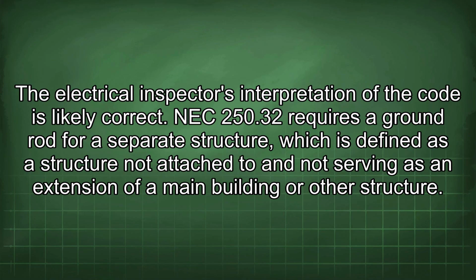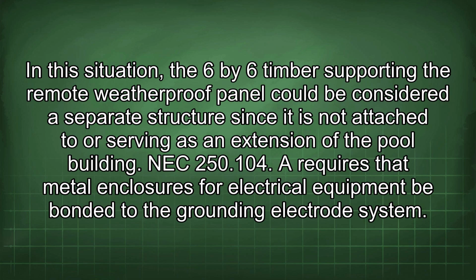The electrical inspector's interpretation of the code is likely correct. NEC 250.32 requires a ground rod for a separate structure, which is defined as a structure not attached to and not serving as an extension of a main building or other structure. In this situation, the 6x6 timber supporting the remote weatherproof panel could be considered a separate structure since it is not attached to or serving as an extension of the pool building.